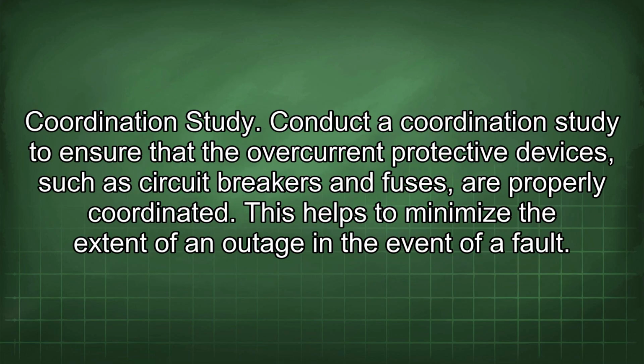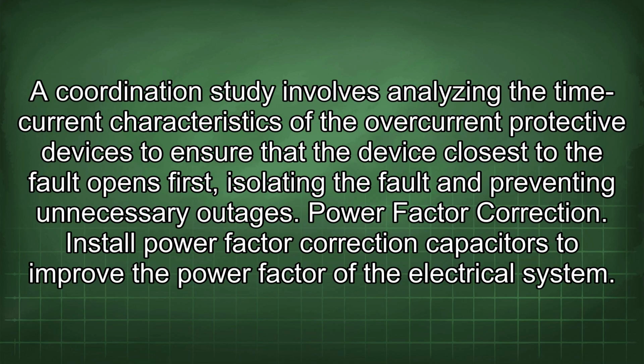Coordination study. Conduct a coordination study to ensure that the overcurrent protective devices, such as circuit breakers and fuses, are properly coordinated. This helps to minimize the extent of an outage in the event of a fault. A coordination study involves analyzing the time current characteristics of the overcurrent protective devices to ensure that the device closest to the fault opens first, isolating the fault and preventing unnecessary outages.